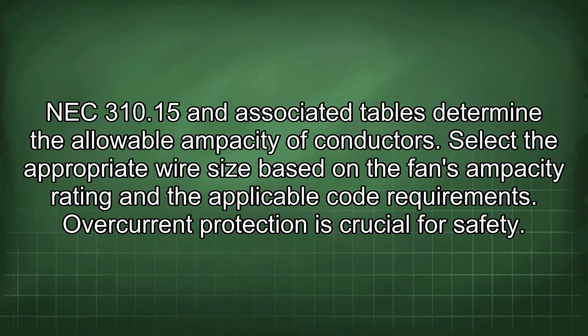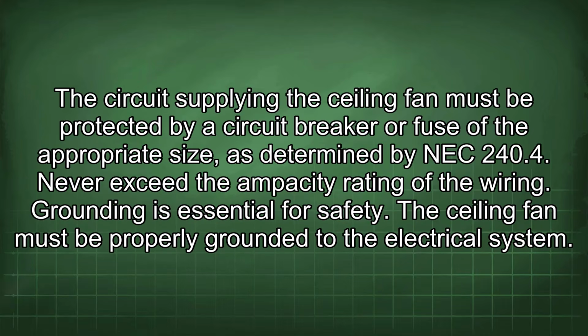NEC 310.15 and associated tables determine the allowable ampacity of conductors. Select the appropriate wire size based on the fan's ampacity rating and the applicable code requirements. Overcurrent protection is crucial for safety. The circuit supplying the ceiling fan must be protected by a circuit breaker or fuse of the appropriate size, as determined by NEC 240.4. Never exceed the ampacity rating of the wiring.